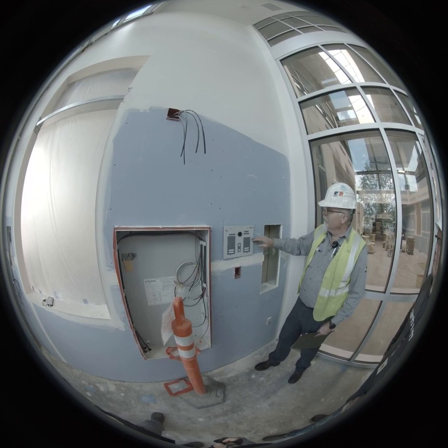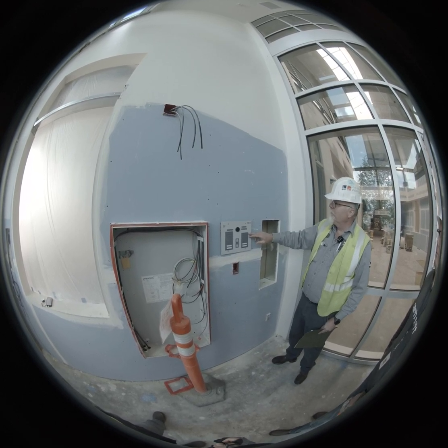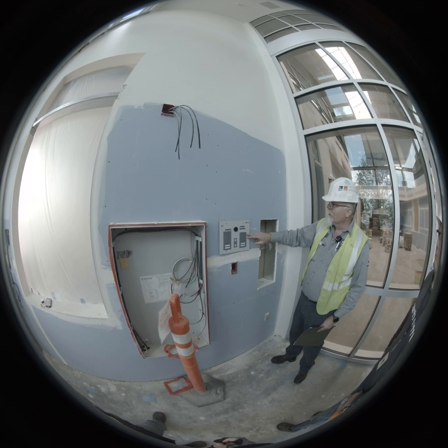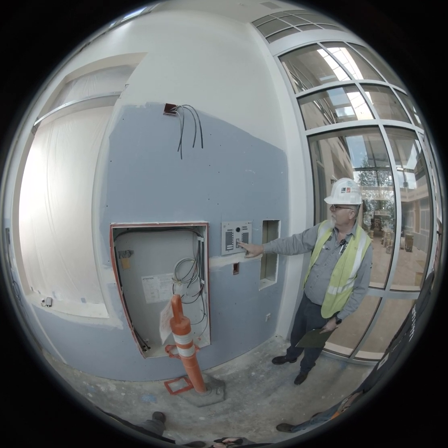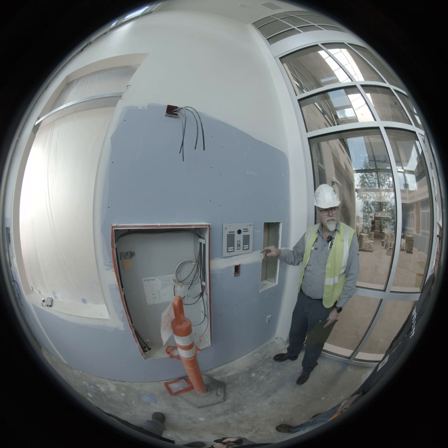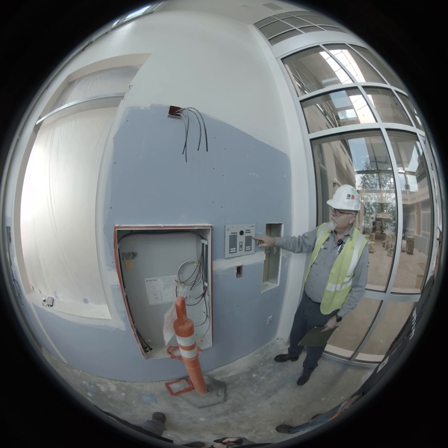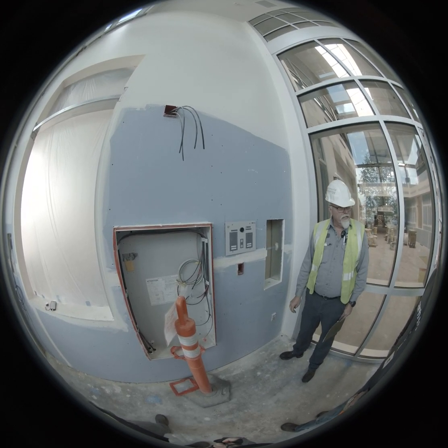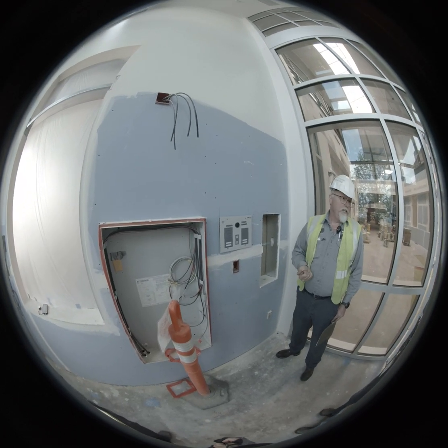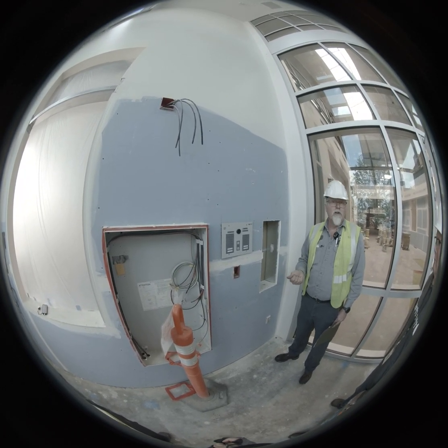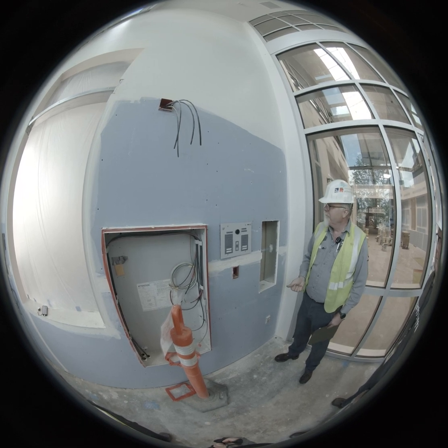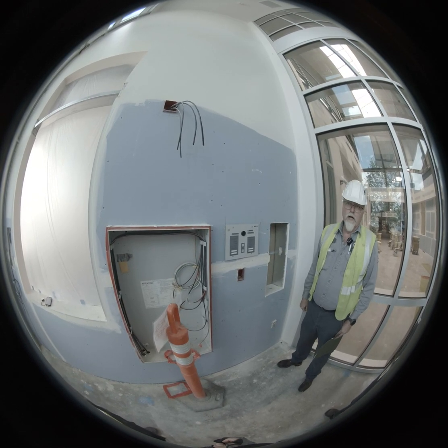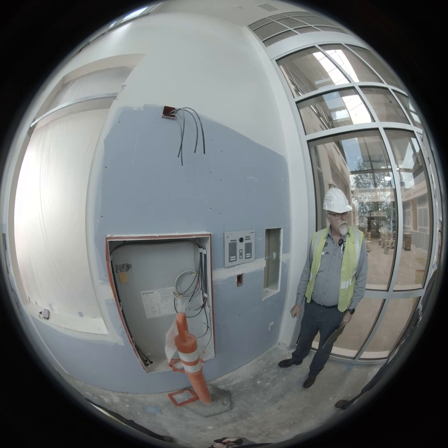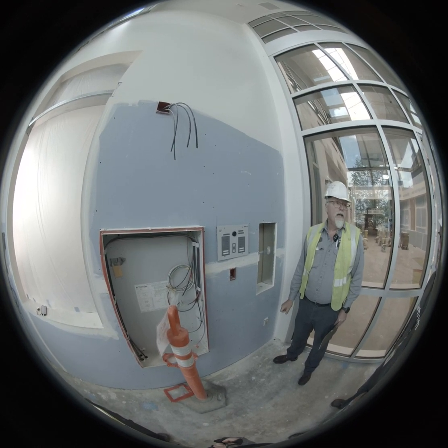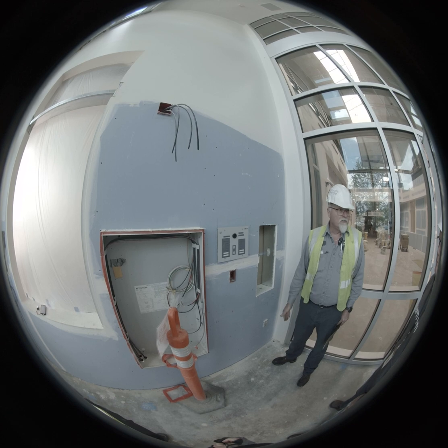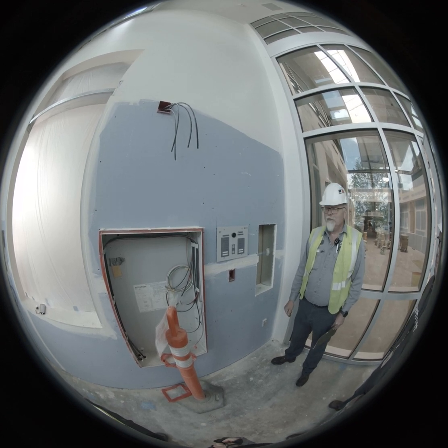Okay. Getting to the other side, we have the pre-alarms. You should see these here are yellow and annoying. These tell you that you're approaching a shutdown point. It's not at a point where it's shutting down yet, but it's getting close, and if you don't do something, then bad things could happen. Low fuel level, of course, is on the warning side, and it will come on at roughly 50%, like we discussed earlier. That will probably be one you're going to see quite often.